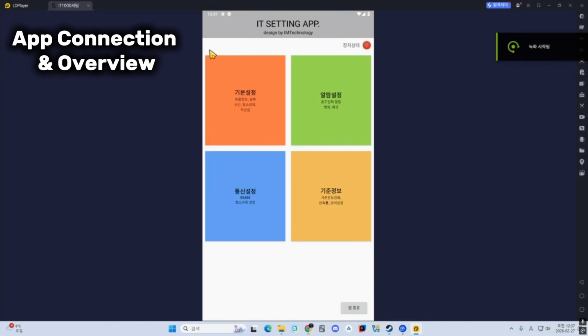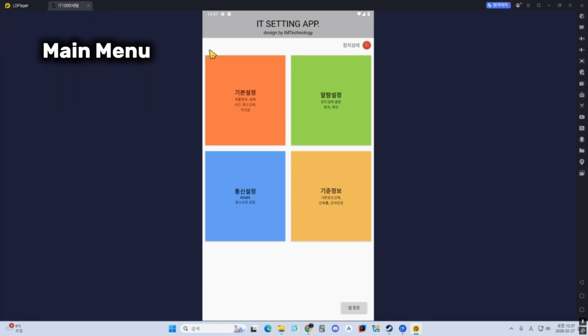The IT1000 allows you to easily change the settings using a dedicated smartphone application. By connecting the cable to your phone, you can check the device status and modify parameters instantly in the field. Once you run the application, you will see 4 main menus: device status for real-time data, product info for device details, and alarm settings to manage the alarm history.